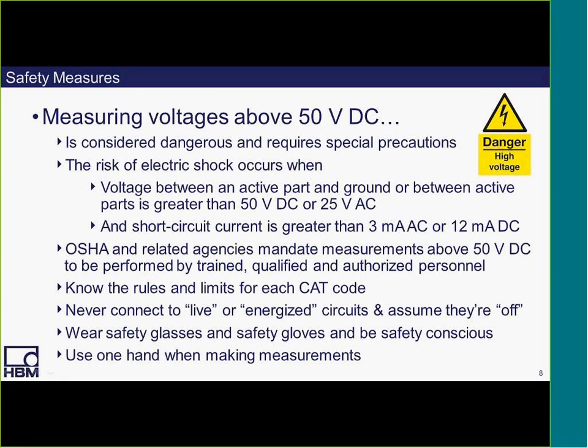In fact, OSHA and related agencies mandate measurements above 50 volts DC to be performed by trained, qualified, and authorized personnel. So you want to be sure to know the rules and the limits for each CAT code, which we'll talk about in a moment, and never connect to live or energized circuits, and never assume that they're off. You want to be sure to wear safety glasses and safety gloves and be safety conscious, and never use one hand on, for example, a metal pipe while attempting to connect to a high voltage point with the other hand. You want to make sure to put one hand in the pocket and use one hand to make the measurement.